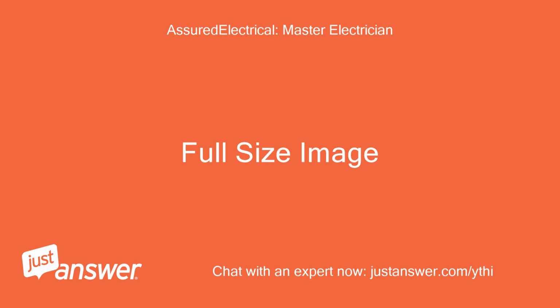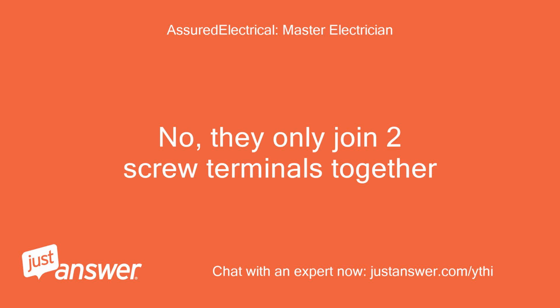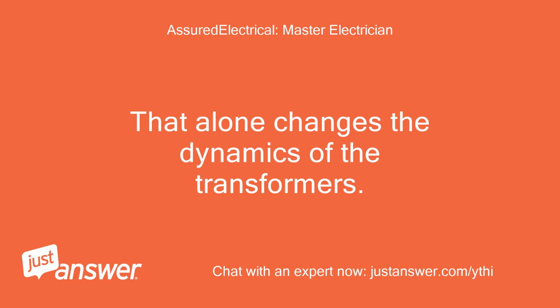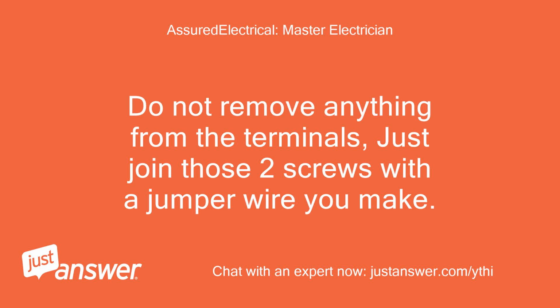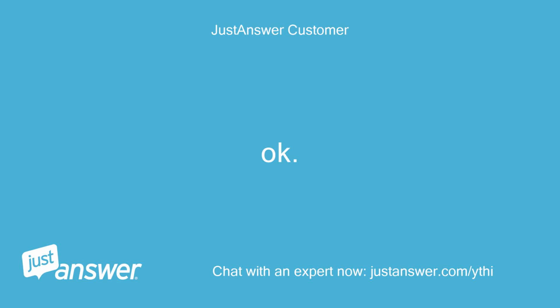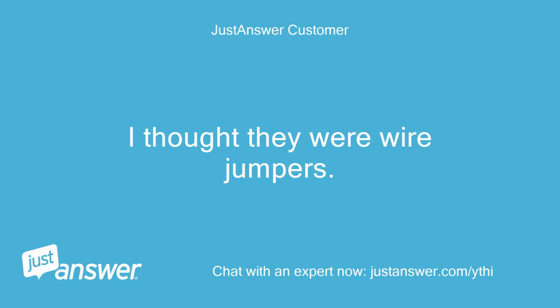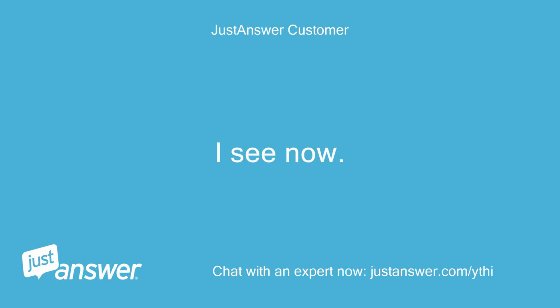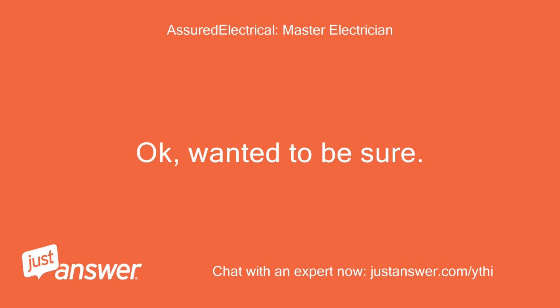Full size image. No, they only join 2 screw terminals together. That alone changes the dynamics of the transformers. Do not remove anything from the terminals, just join those 2 screws with a jumper wire you make. Okay. I thought they were wire jumpers. I see now. Okay, wanted to be sure.